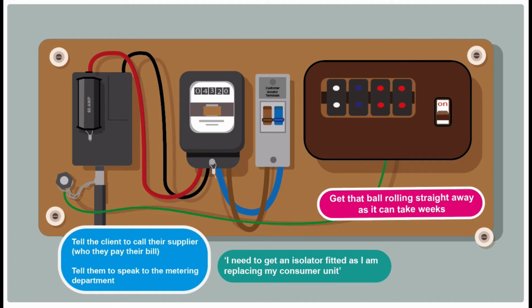They'll come, connect it into the meter. They'll also connect it back up to the fuse board if you want them to. I haven't put the tails into the fuse board here. They've just got their tails into their end. This is the contractor's end. We're allowed to open this bit because we can isolate it safely. It's all disconnected. We can put our tails in there and then we can work safely on the new board. So yes, get them to call the meter people straight away and get them to fit an isolator.